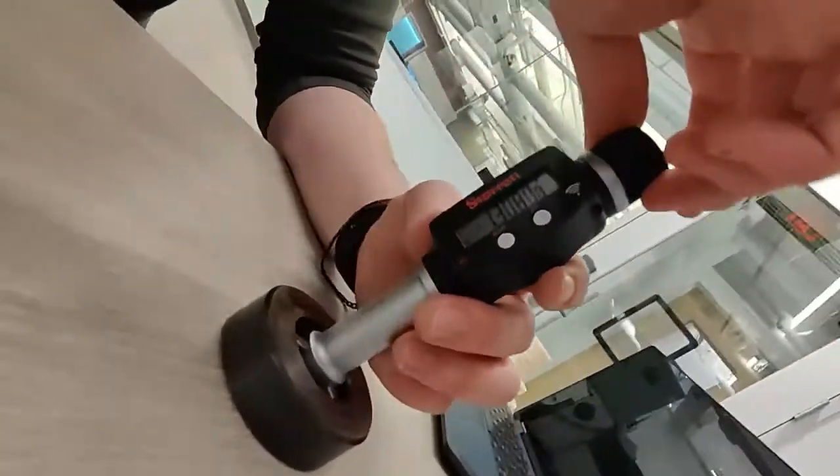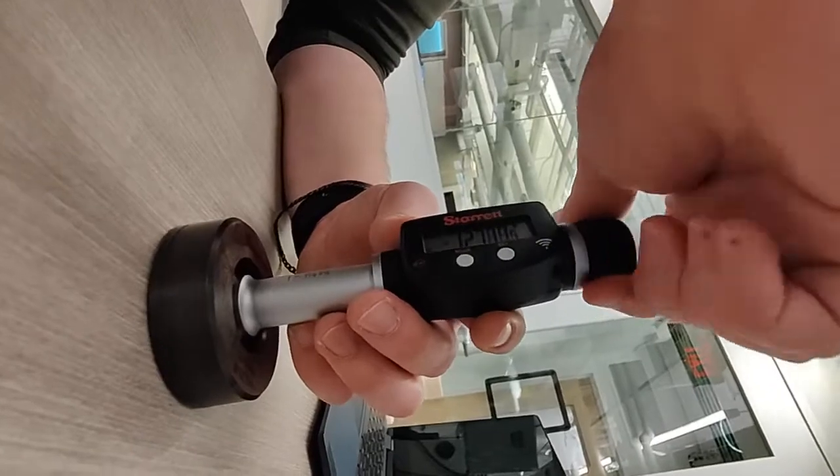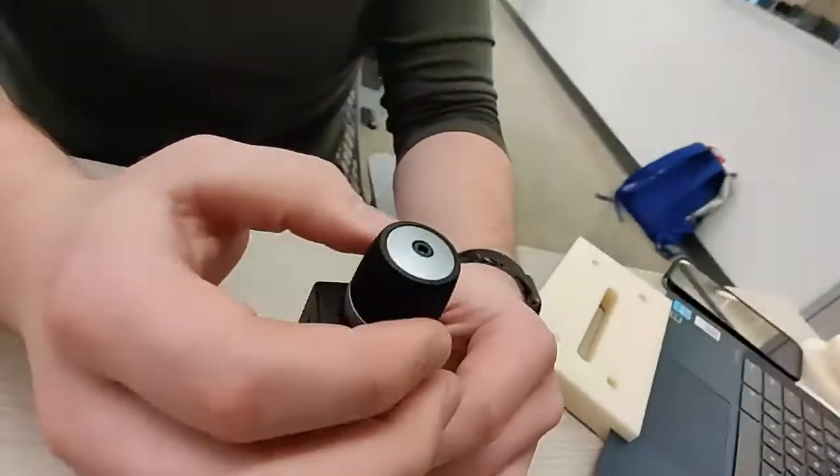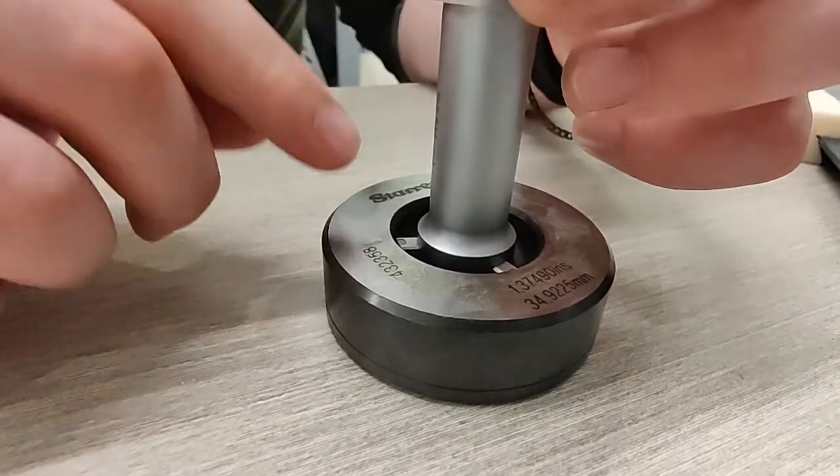We're going to insert the bore mic into the ring gauge and rotate the spindle clockwise until the ratchet clicks so we don't put excess pressure on the surface.